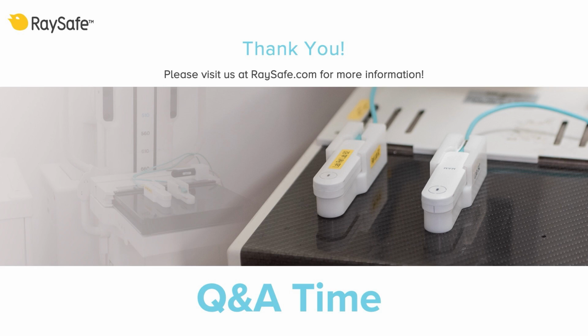What model should I get? I didn't understand the various models that are available. Okay, we have 3 different models. One is the ambient dose model used for measuring in sievert or in Rem. We have one model in air kerma version used for measuring in gray, rad or Röntgen. But we also have the full version, and this version can measure the 2 which I mentioned, and can also be used as a contamination meter by removing the lid. It is only the full version that can be used as a contamination meter with a naked GM pancake.